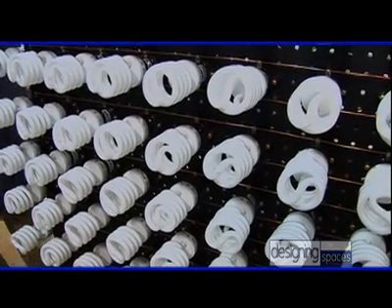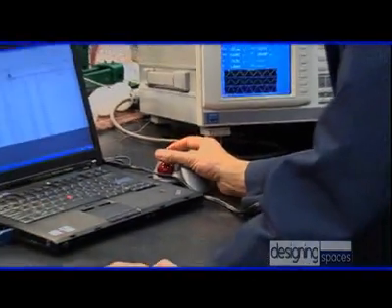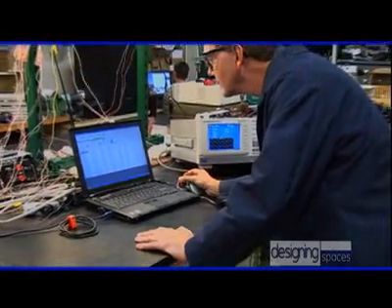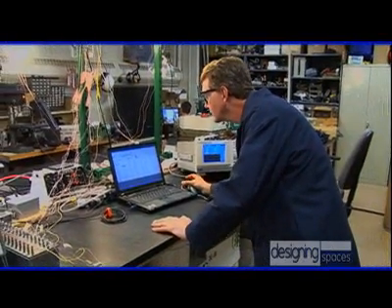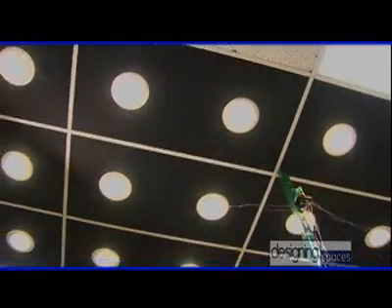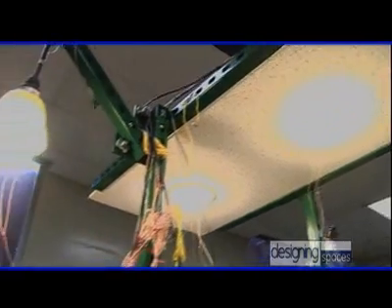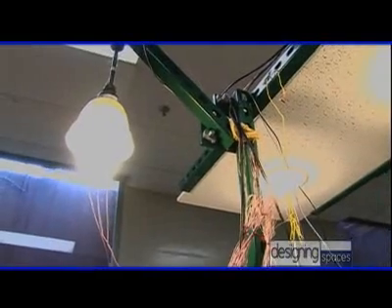You save a lot of money, but there are some differences with compact fluorescent light bulbs. One of the things that the packaging will very often say is, don't use with a dimmer. So we're doing some basic research using dimmers. You look up at the ceiling here, you see a lot of light bulbs up there, compact fluorescent, with cheesecloth around them. We want to see what fire issues might occur if you do use one with a dimmer.